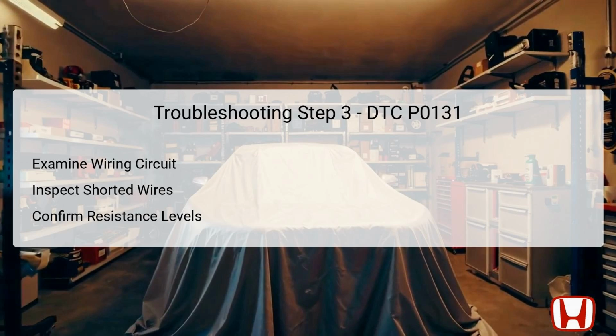Once secured, the resistance across the wires such as LAF-VG, LAF-VN, LAF-CP, and LAF-CA should be checked, ensuring that each in-ground inspection shows more than 1 mega-ohm, confirming no short circuit conditions exist. This step is crucial to avoid overlooking potential wiring faults that could mislead the diagnosis.